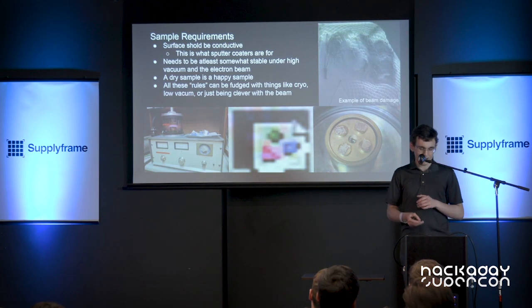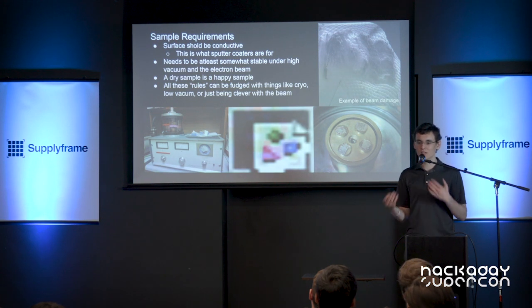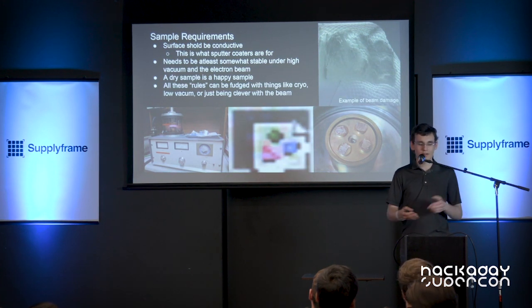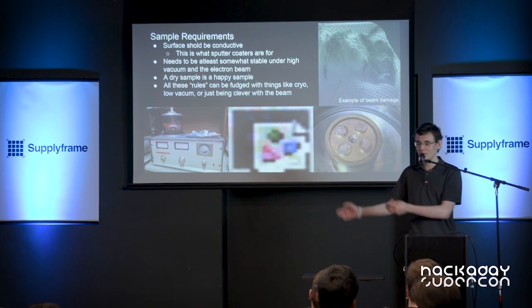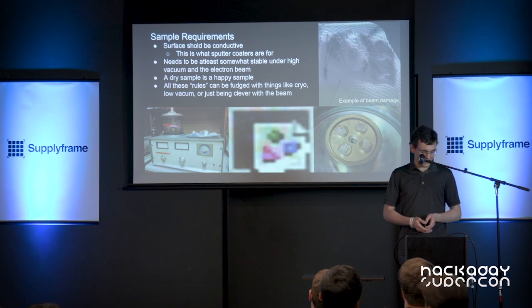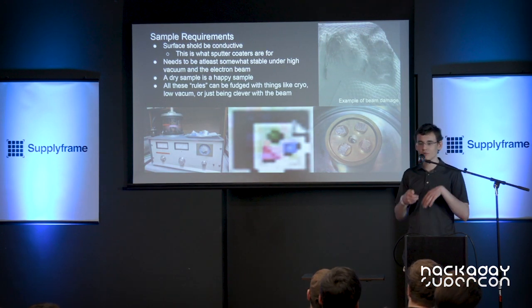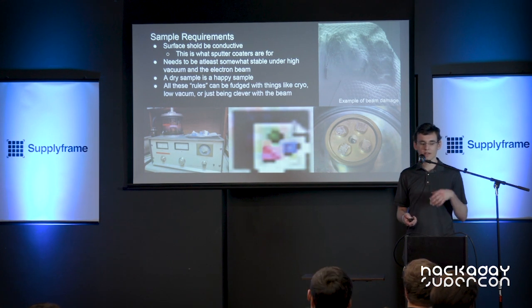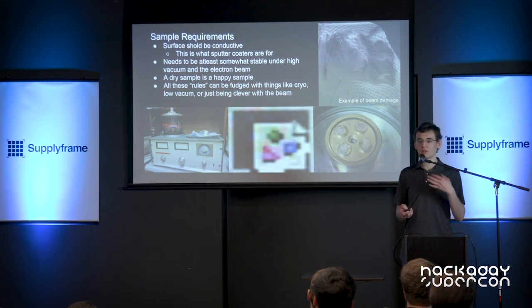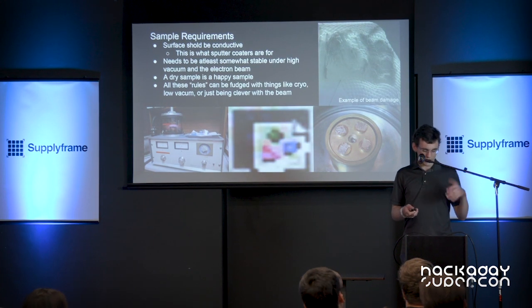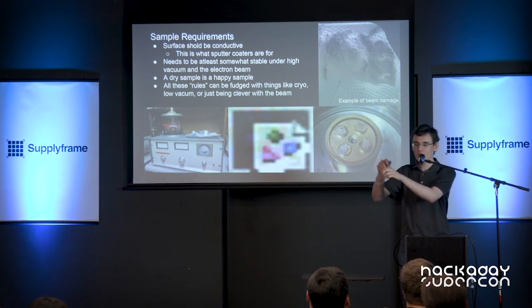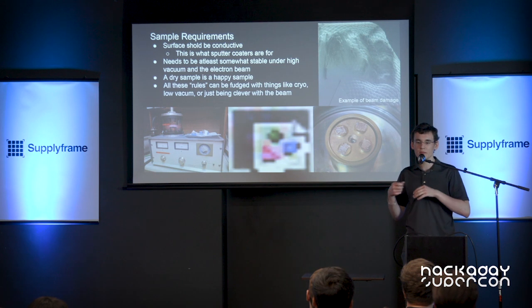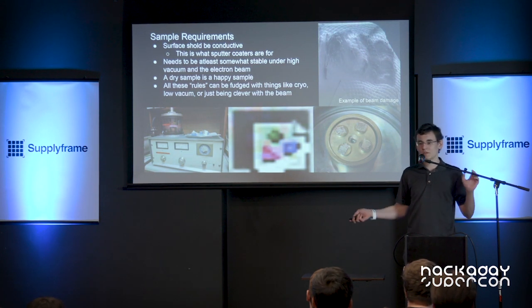The hobbyist scopes tend not to use cryo-SEM because it's a really expensive setup. But we're hackers — we can figure this out. You take a block of aluminum, you freeze it, and then you put that in the microscope, and it stays cold enough long enough to keep your sample at liquid nitrogen temperatures. So you've just recreated a $100,000 device with scrap metal. You can also use low vacuum mode, where you degrade the vacuum inside your specimen chamber. Or just be clever with the beam — you can focus somewhere, then quickly move the beam to where you actually want to image, and gather data as quickly as possible to minimize the damage the beam does to the sample.